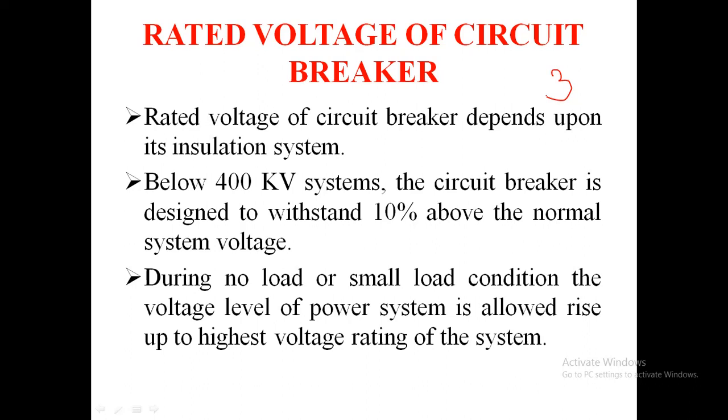A circuit breaker must be assigned two voltage ratings: one corresponding to the maximum nominal system voltage, and the other the maximum design voltage, which indicates the maximum operating voltage that should not be exceeded.